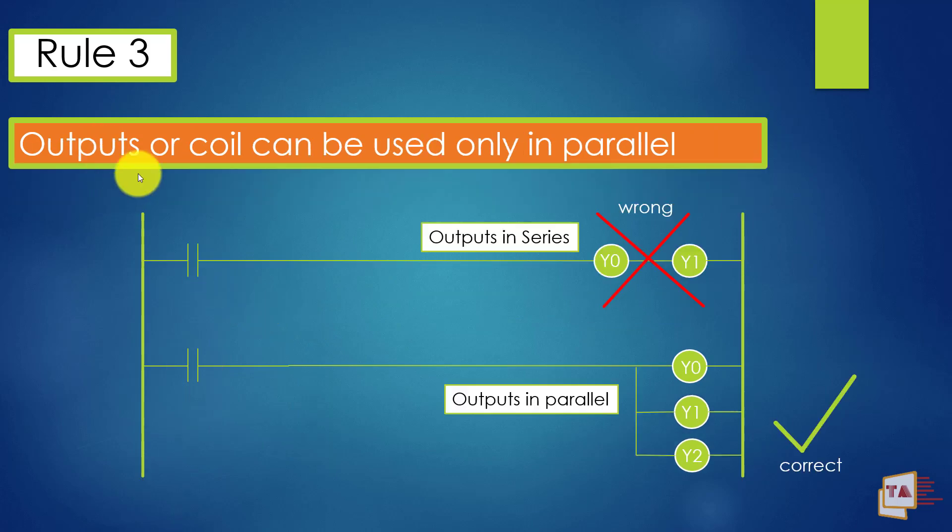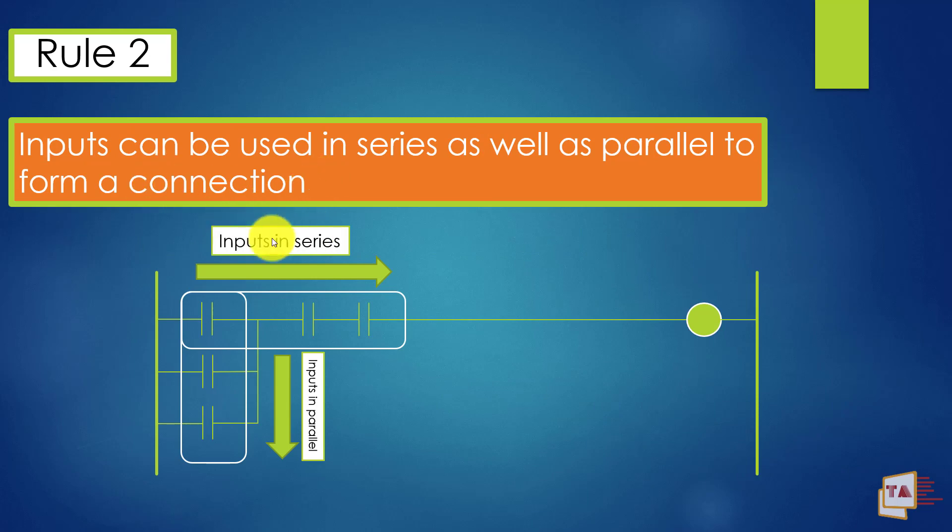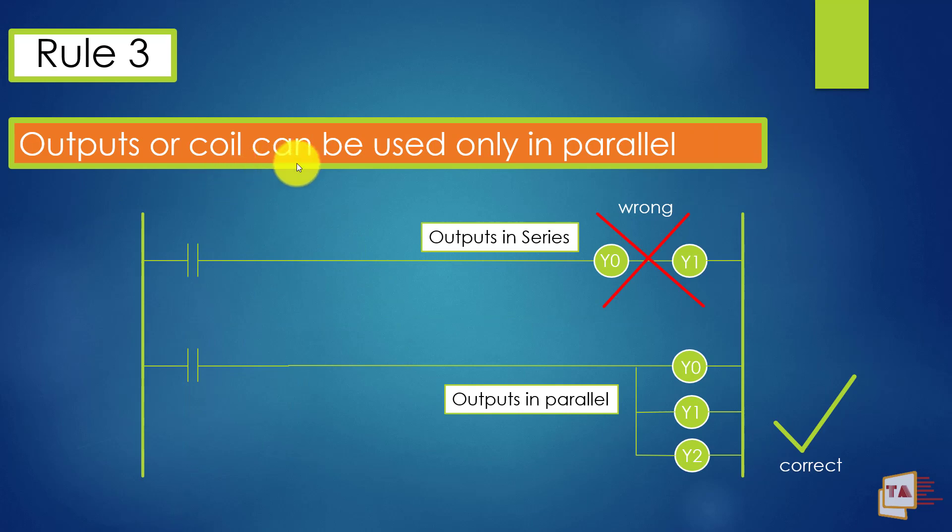Next rule number three: outputs or coil can be used only in parallel. Inputs, we can use in series and parallel also, but here outputs or coil can be used only in parallel. You cannot use it in series. See here, I have mentioned the output in series. So this is the wrong method. If you put the output coils like this, software won't accept the line. Maybe it will throw some error. So if you place the outputs in parallel, this will be okay. This is the correct method to place the outputs.